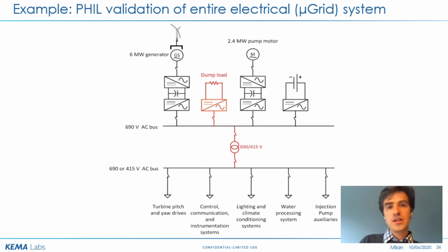So you have the inverters, but all the loads and generators are simulated, and you could still have realistic emulation results to be able to see under which circumstances and which corner cases you need to look at controls and to design and specify requirements for the individual components to be able to engineer the system without any copper or cables being made or components being made yet.